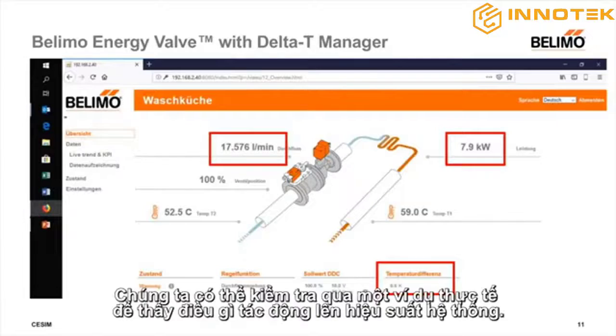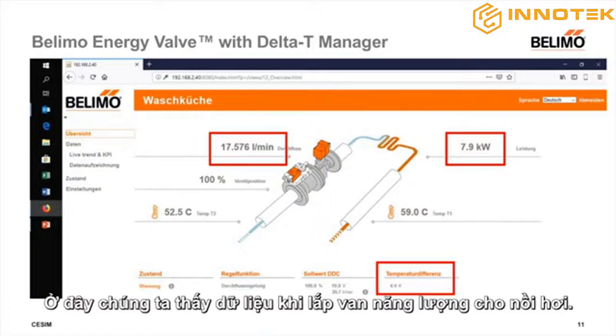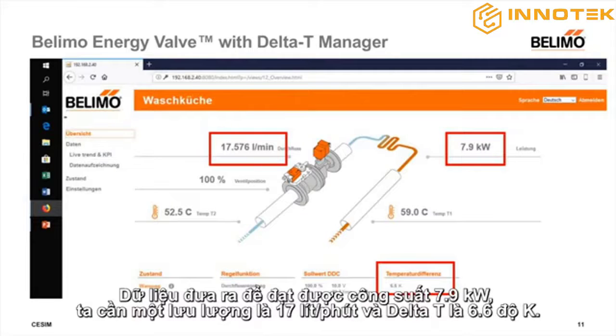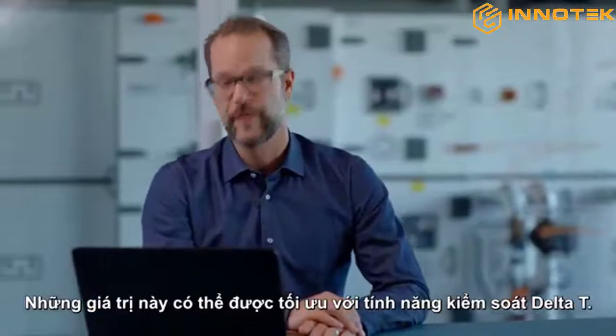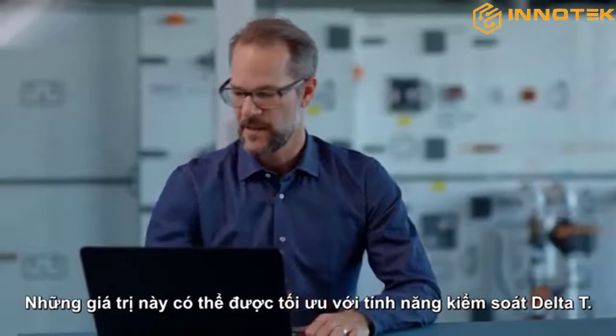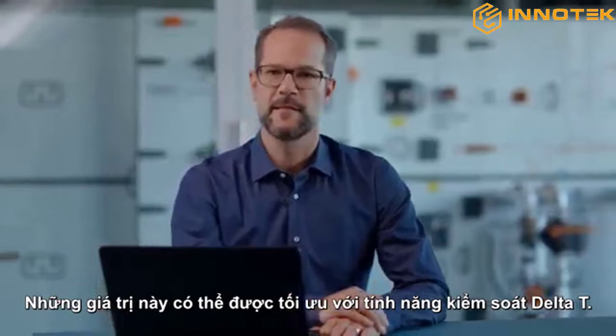We can see from a practical example what such an increase in energy efficiency really means. Here we can see the data of an installed energy valve with a condensing boiler. The installation data show an output of 7.9 kilowatt, which is achieved with a flow rate of 17 liters per minute and a differential temperature of 6.6 Kelvin. These values can be massively improved with the DeltaT manager, as we can see here on the next slide.